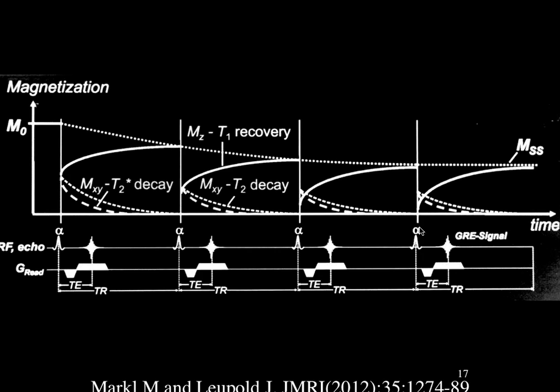In steady state, you give a pulse, do a gradient refocusing, get a signal, and put in gradients different ways to give each signal a different phase encoding to fill different parts of k-space. The TR can be very short — 25 to 50 milliseconds instead of the typical 500 or 3000 milliseconds. If it's 50 milliseconds instead of 500 milliseconds, you can decrease the acquisition time by a factor of 10.